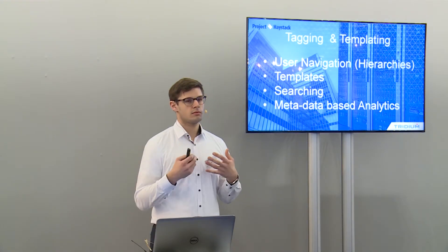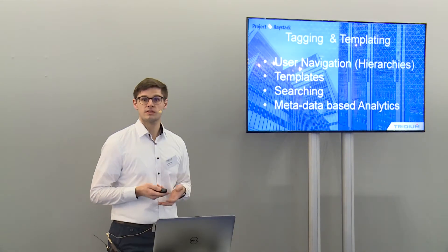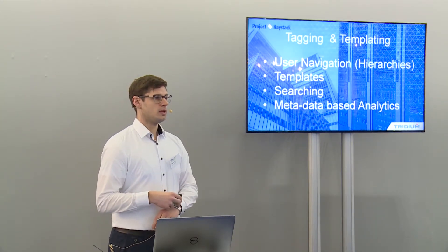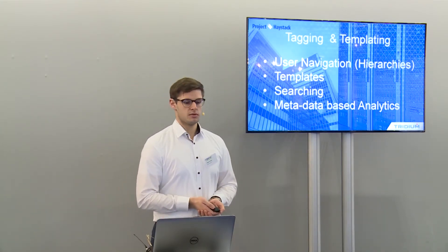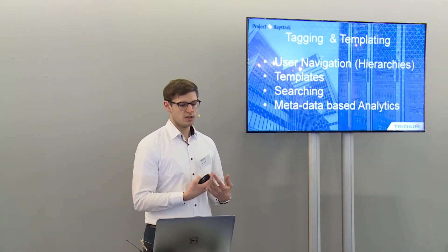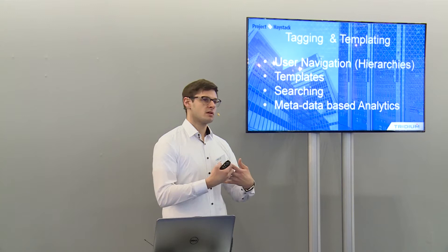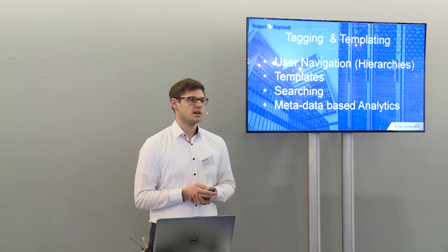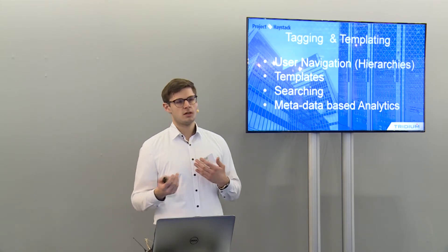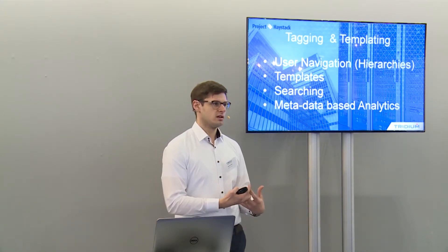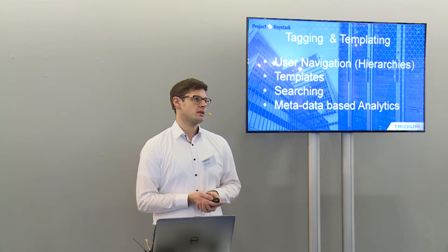Talking about data analysis: we have analytics capabilities and we add metadata to our data points and devices in the Niagara network through tagging. We support Project Haystack so that metadata is common and consistently known across all devices. We use this tagging functionality to create user navigation — what we call hierarchies — so the user can automatically navigate through the system in the browser.